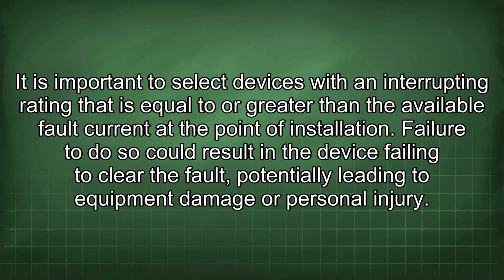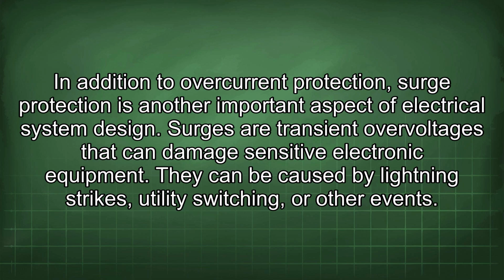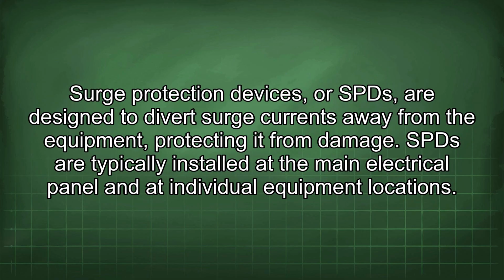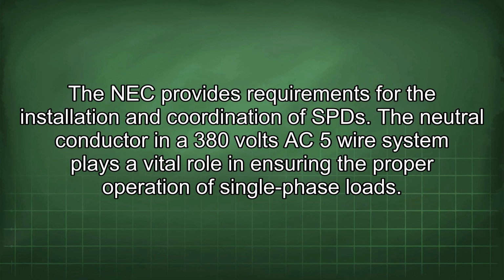In addition to overcurrent protection, surge protection is another important aspect of electrical system design. Surges are transient overvoltages that can damage sensitive electronic equipment. They can be caused by lightning strikes, utility switching, or other events. Surge protection devices, or SPDs, are designed to divert surge currents away from the equipment, protecting it from damage. SPDs are typically installed at the main electrical panel and at individual equipment locations. The NEC provides requirements for the installation and coordination of SPDs.